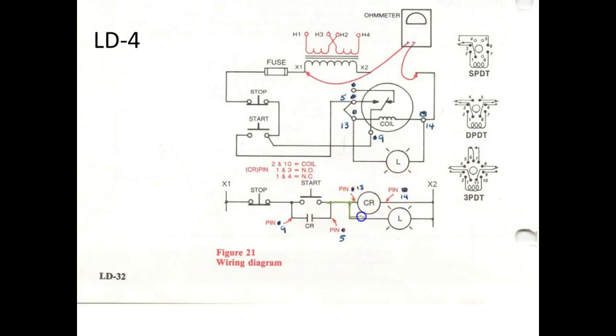Which is all, but it's also going to turn on the light, right? At the same time. Then I release the start button. What's going to happen? Well, as soon as the relay energizes, it's going to close that guy, and now it's got a secondary path. So this guy's going to seal in, right?